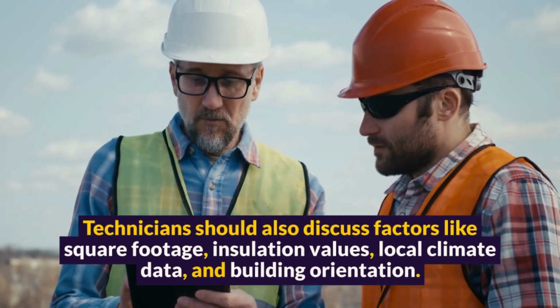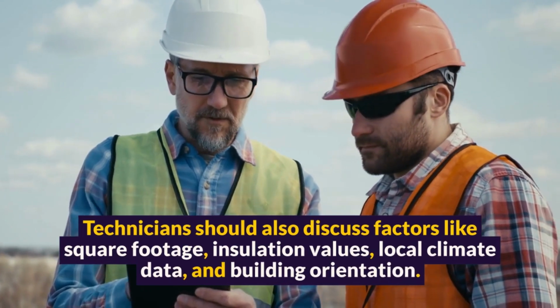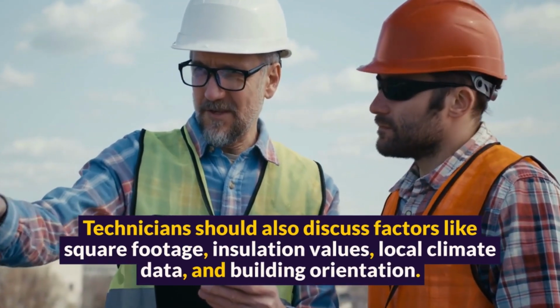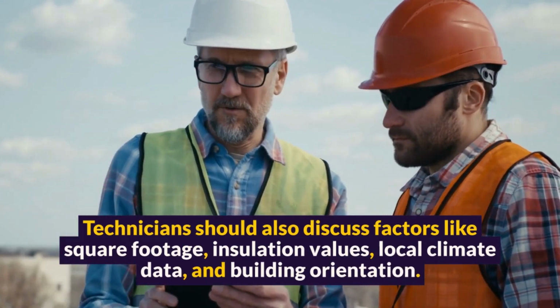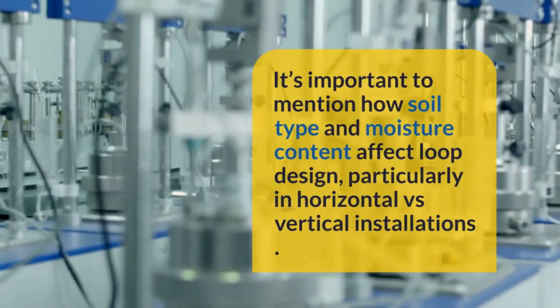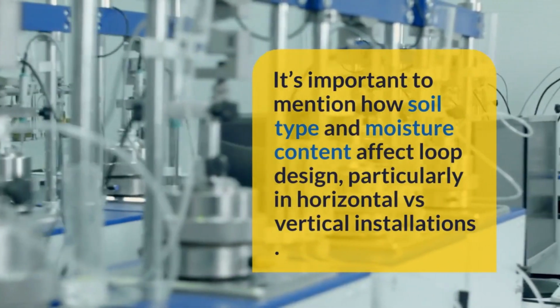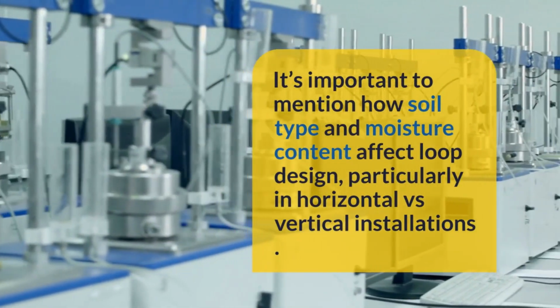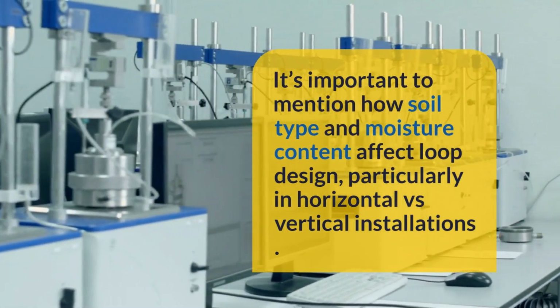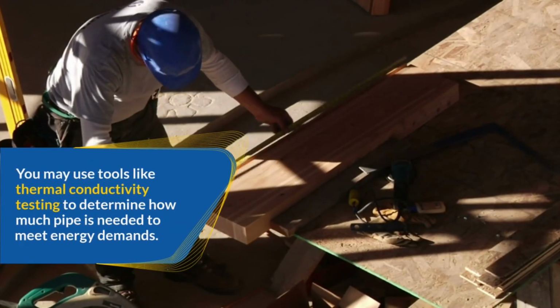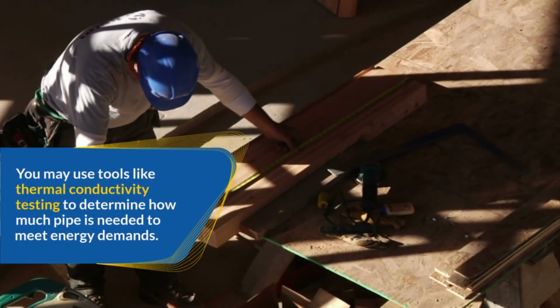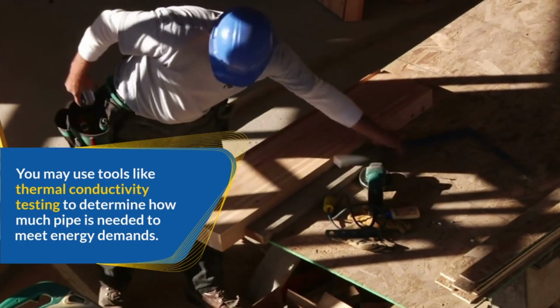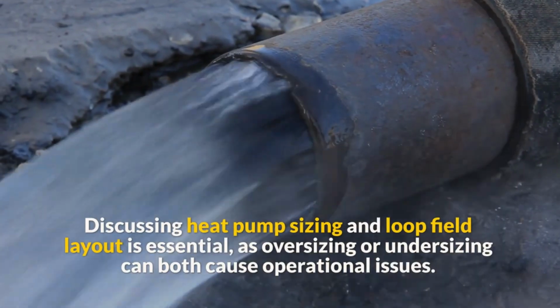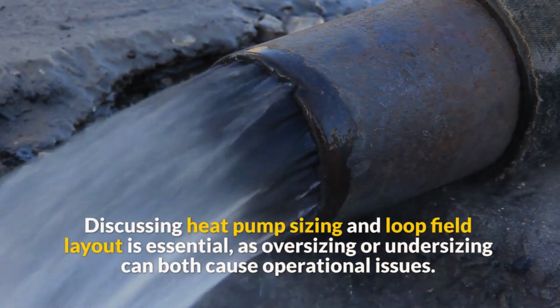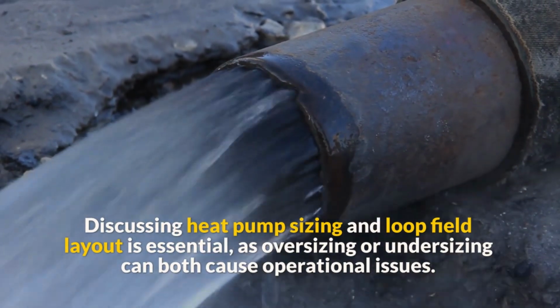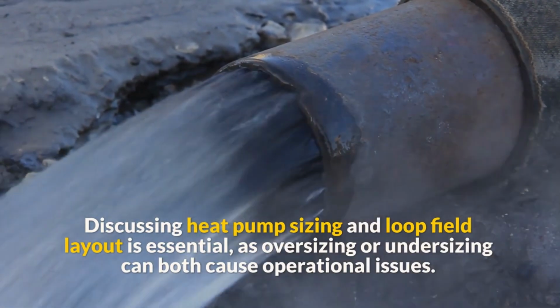Technicians should also discuss factors like square footage, insulation values, local climate data, and building orientation. It's important to mention how soil type and moisture content affect loop design, particularly in horizontal versus vertical installations. You may use tools like thermal conductivity testing to determine how much pipe is needed to meet energy demands. Discussing heat pump sizing and loop field layout is essential, as oversizing or undersizing can both cause operational issues.